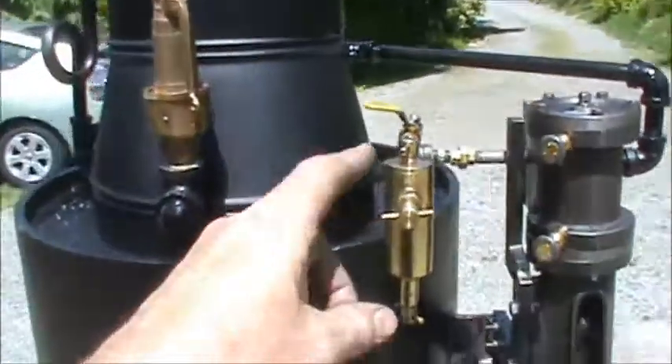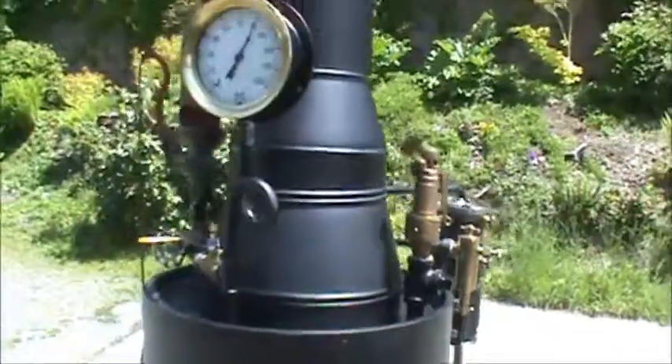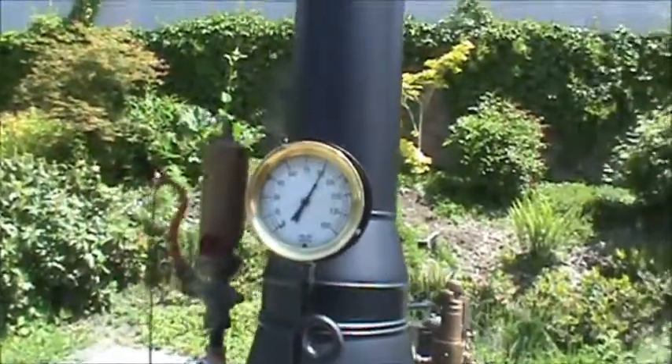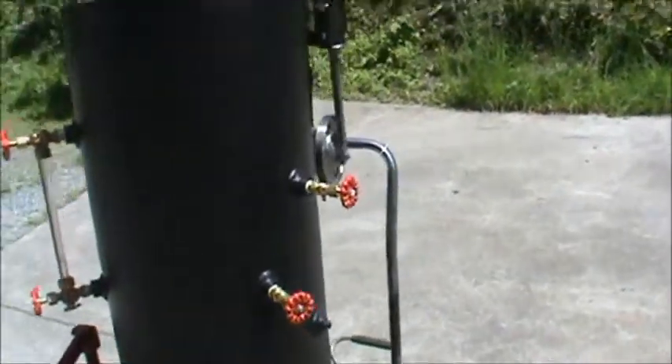Boiler right here. Pop-off valve on the boiler set at 125. It's been running here for a while holding pressure at about 90 pounds. Looks good. Trycock on it.